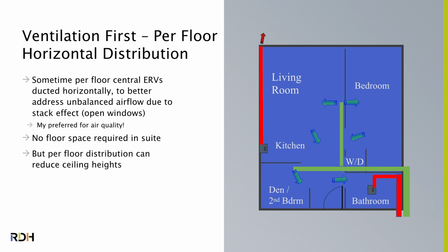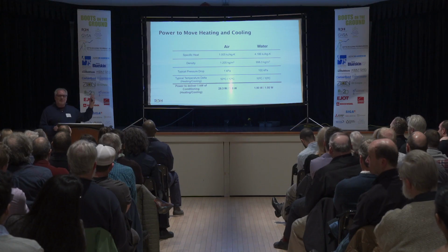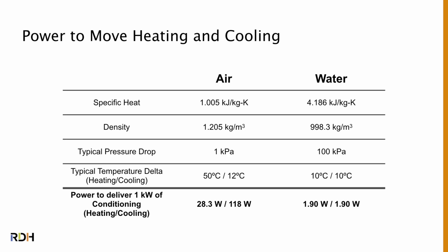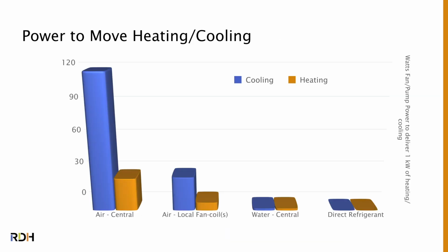Now, moving on to heating and cooling. I think most people know this, but if you ever want to see it graphically and visually, if you want to move heat and cool around the building, you can do it with air, you can do it with water, and these days you now can do it with phase change materials we call refrigerants. This is roughly the math of how much energy it takes to move 1 kilowatt of heat or cooling, but I like to show it in bar graphs. Moving hot air around is expensive. Moving hot water around is a lot easier, and moving hot and cold refrigerant doesn't cost anything.